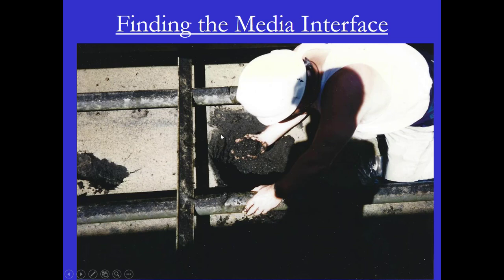Another thing you want to look for is if you have a dual media filter — this filter in particular is anthracite and sand. How big is the interface between the anthracite and the sand? It shouldn't be more than a couple of inches if the filter is in good condition. If it's six, seven, or eight inches, that's an indication either the media wasn't properly sized or there's a problem with the backwash procedure.